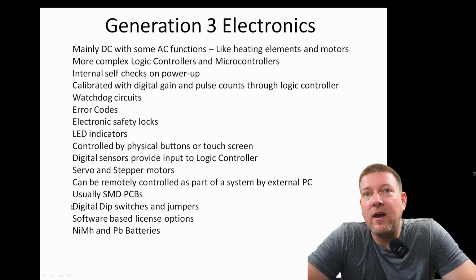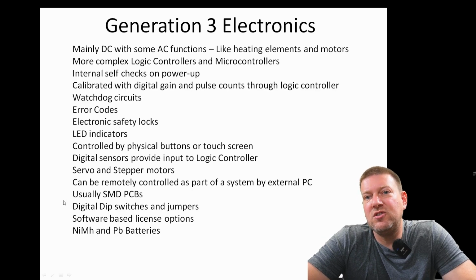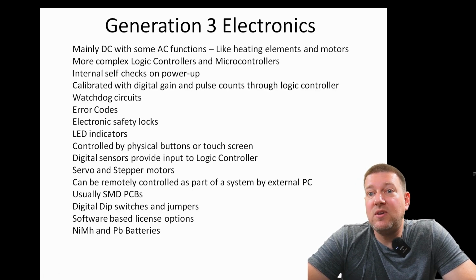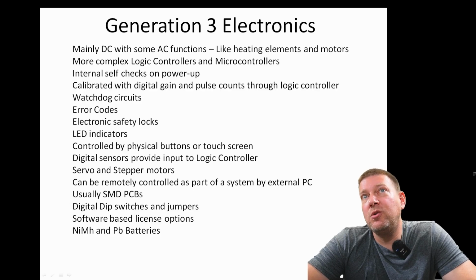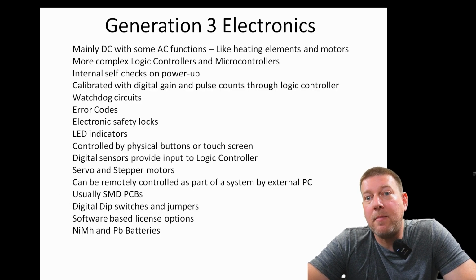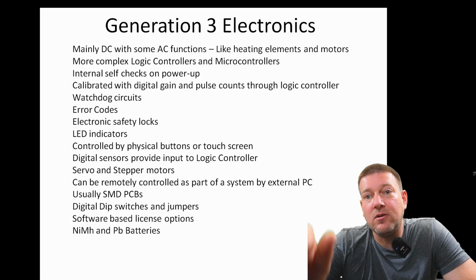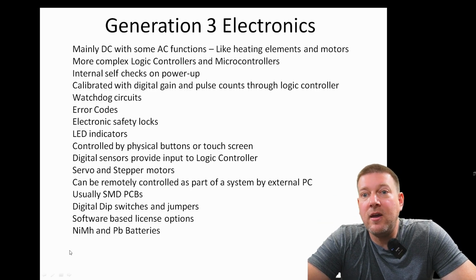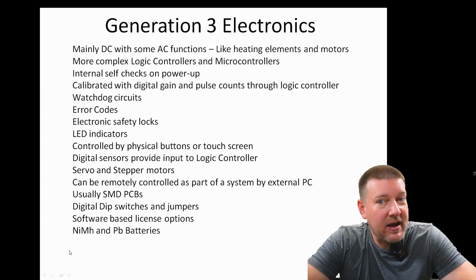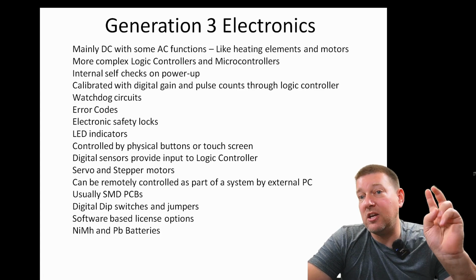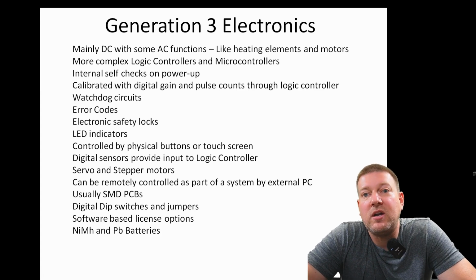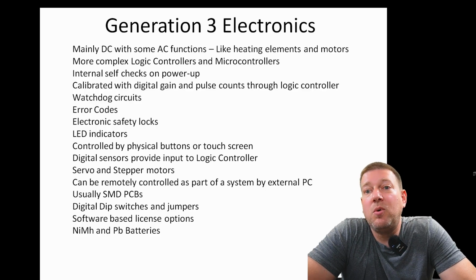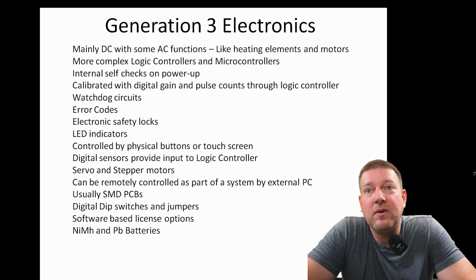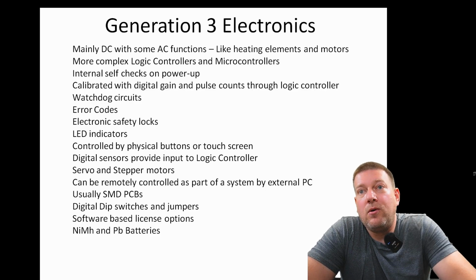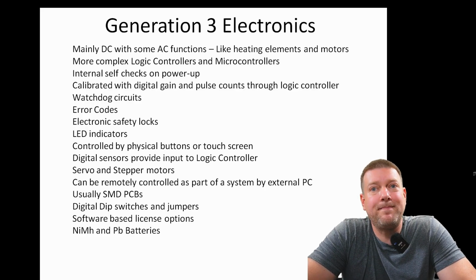We also have digital dip switches and jumpers. Now you can go into service mode or Biomed mode and set certain jumpers or parameters, like switching from kilograms to pounds. That could be a digital jumper or digital switch, versus old style scales where we'd have to physically move a jumper on a PCB to change the functions of the software.